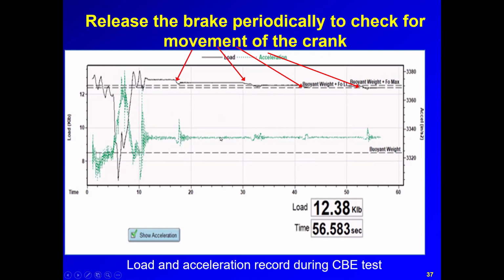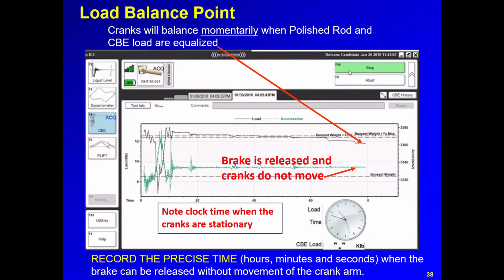It depends a lot on whether you have leakage through the valves or a lot of slippage. In some cases, the slippage may be so large that almost immediately you go past the equilibrium point, and so the test is not feasible. So here is the completed test. If you notice here again, the acceleration signal is stationary when we release the brake here. And so this point is the point you need to identify.